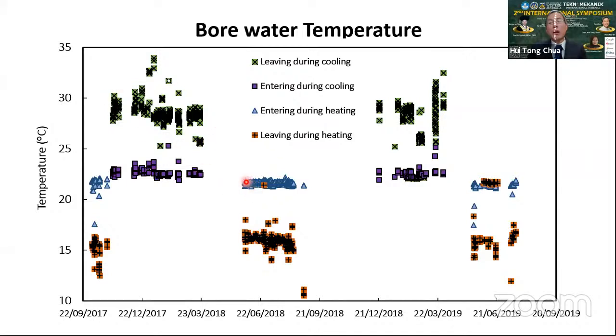Now come to the winter season. The groundwater holds pretty constant yet again, and this is the spent groundwater temperature having had its energy extracted by the heat pump. This is then returned underground. You can see that over the span of 2 years, the groundwater temperature remained practically constant throughout, which is very gratifying, so that it does not exert any discernible environmental disturbance to the groundwater system of the Yarragadee aquifer of the Perth metropolitan area, which has a salinity of about 250 ppm, which is practically fresh water.